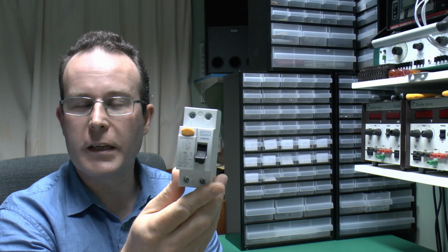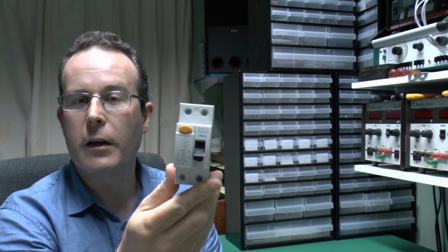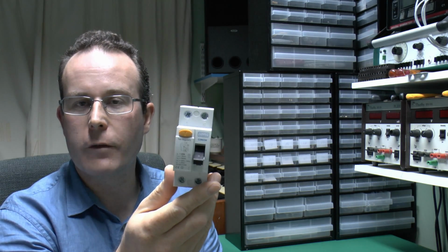And these things really are lifesavers, because exactly the point of them is to disconnect the supply if you accidentally come in contact with a live wire, something which fuses and circuit breakers will not protect you against, as the current flowing there would be far too small to trip even the smallest 6 amp circuit breaker, and it would essentially just continue to pass the current through your body until some other method of disconnection occurred.